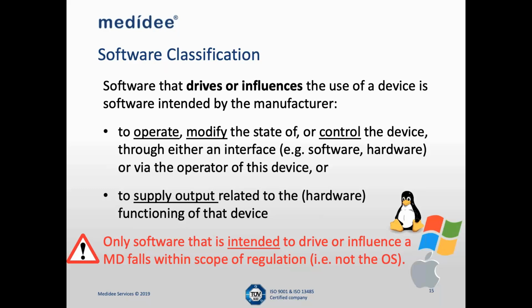Also, when you say that a software is intended to drive or influence a medical device, it is only necessary to include the software that is directly affecting the performance, directly driving or influencing a medical device. There can be a lot of software which may have an ability to influence, but which is not really intended to. So it is always based on the intended purpose. Try to look from the perspective of the intended purpose. If the software is in a position to drive or influence the usage of the principal medical device in question, and only when you can confirm that the software in question is influencing or driving the usage of the medical device, then it is important for such software to fall within the scope of the regulation, but not in general.